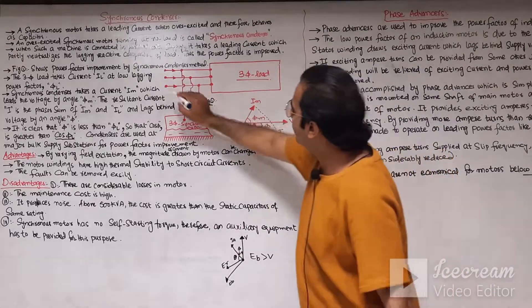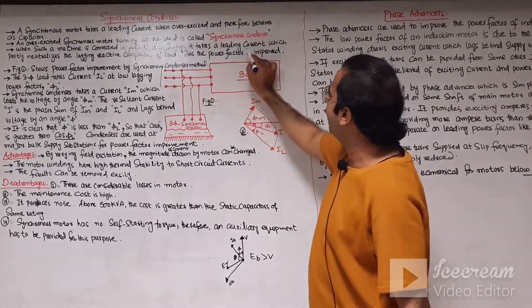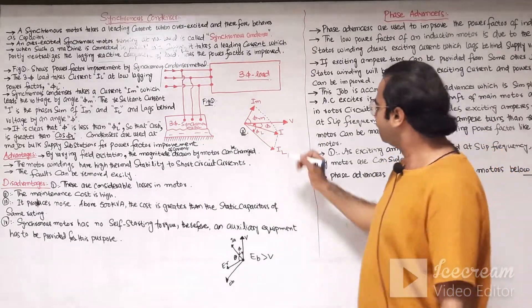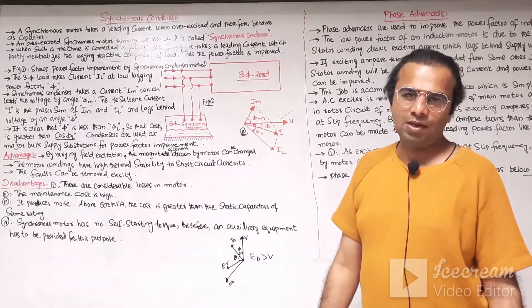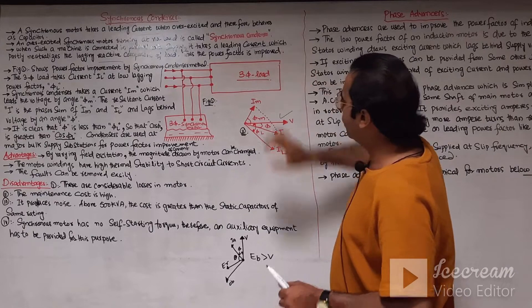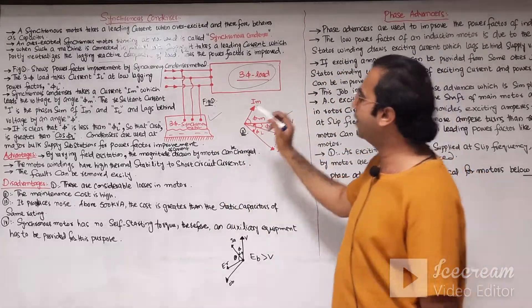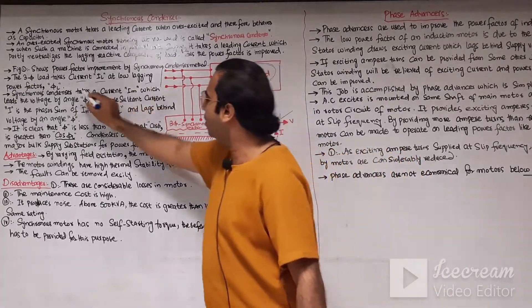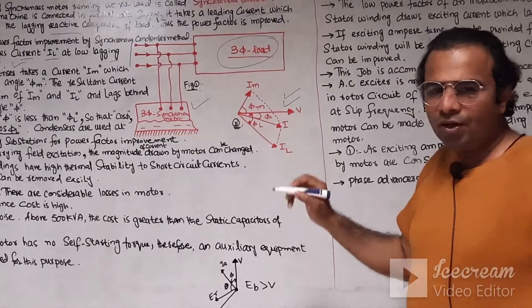When such a machine is connected in parallel with the three-phase supply, it takes leading current and partly neutralizes the lagging reactive component of the load, improving the power factor of the three-phase load. This is the phasor diagram of the three-phase synchronous condenser — a three-phase synchronous motor running at no load behaving like a synchronous capacitor. Figure one shows the synchronous motor connected along with the three-phase supply to improve the power factor of the three-phase load.